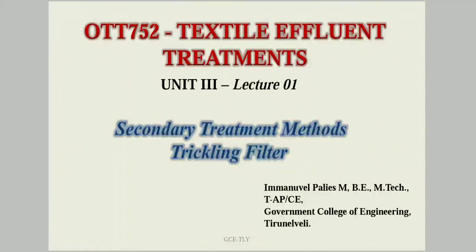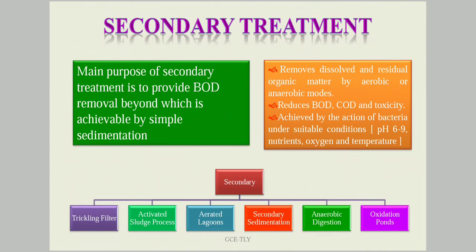The main purpose of secondary treatment is to remove the BOD — that is, all the organic content present in the wastewater coming from the primary clarifier. This removes BOD, COD, and toxicity, which is achieved by the action of bacteria under a pH range of 6 to 9 and under suitable nutrients, oxygen, and temperature.